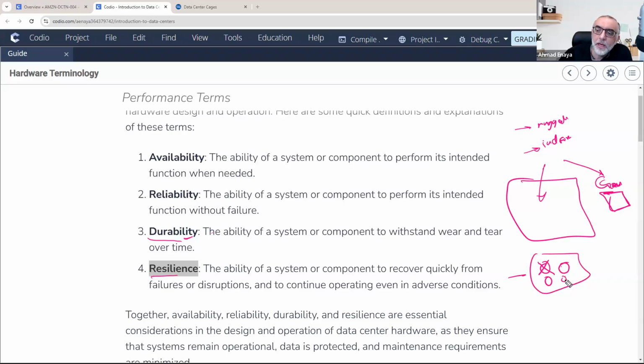You may have redundancy, but without proper software, protocol, or design, it might take a minute for the system to recover. So you have redundancy, but the system takes a long time to recover, which means it has bad resiliency. Resiliency is about the logic connecting redundant components so that in case of failure, the other part takes over the service immediately. It's about how quickly the system can recover in case of failure.